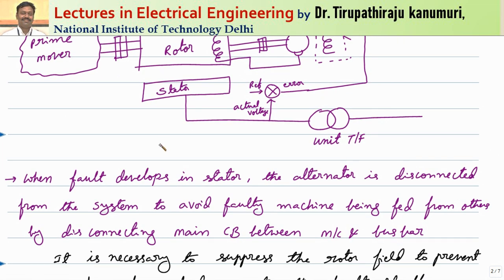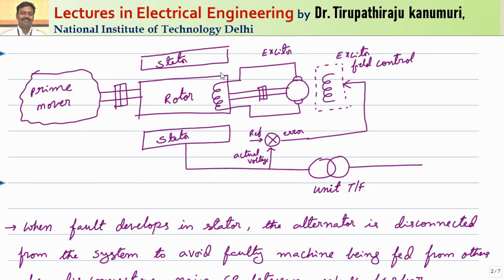When a fault develops in the stator, the alternator is disconnected from the supply. But that is not sufficient for the case of an alternator, because even if the alternator is disconnected, the prime mover is still connected and rotating the exciter. The exciter automatically supplies the field, and as the field is there and rotating, it will continue to produce a voltage and supply the fault — leading to damage of the alternator even though it is disconnected from the grid.